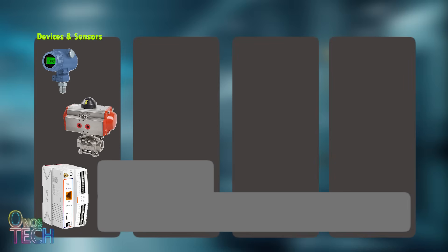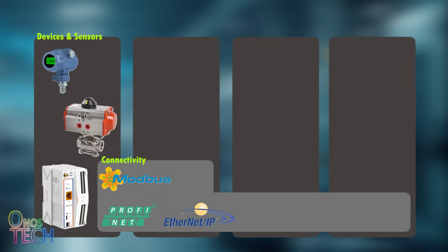The first layer is made up of sensors, actuators, PLCs, and instruments that measure temperature, vibration, pressure, and other parameters. Data is reliably exchanged from this layer in real-time with other layers using various forms of connectivity. Connectivity is the layer that moves data from devices to the edge or cloud using wired or wireless networks in real-time. Common wired protocols include Modbus, Ethernet IP, and Profinet, while wireless options include Wi-Fi, LoRaWAN, 4G, 5G, and Bluetooth. This layer is the backbone of IIoT.